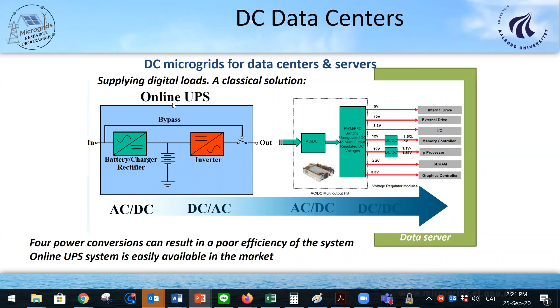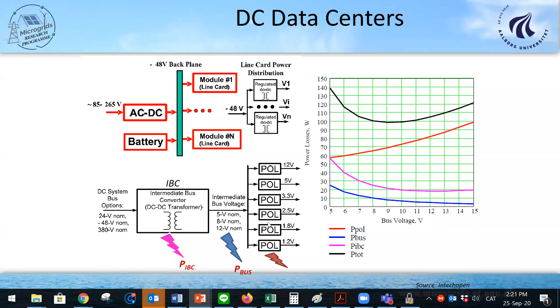By removing the UPS system and instead using just a rectifier, putting in the battery systems, and then using a single DC-DC converter, the efficiency has been increased, at a minimum, between 11 and 14%, which is kind of nice. This project demonstrated that this is effective. We can also regulate the intermediate voltage, because this voltage is connected to a number of point-of-load converters, so the voltage can be adjusted according to the load.